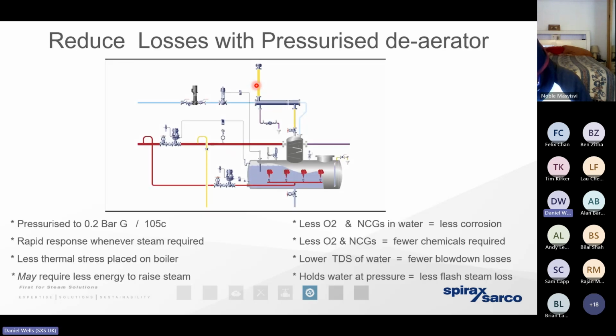So in a small number of applications, generally in the food, beverage, pharmaceutical sector, it's going to be attractive to consider moving away from a hot well, a feed tank that's operating at atmospheric pressure, which therefore means the maximum temperature can only really operate at 85 degrees or thereabouts. But if we can pressurize that hot water that's in storage up to 0.2 bar gauge, it means we can elevate the temperature of the water beyond 105 degrees. So you can appreciate there's going to be a significant energy saving there.